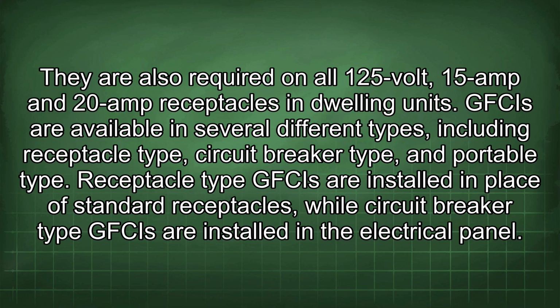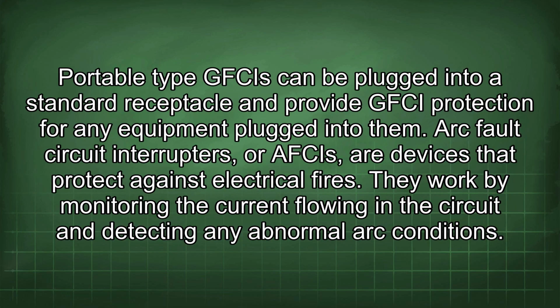Receptacle type GFCIs are installed in place of standard receptacles, while circuit breaker type GFCIs are installed in the electrical panel. Portable type GFCIs can be plugged into a standard receptacle and provide GFCI protection for any equipment plugged into them. Arc fault circuit interrupters, or AFCIs, are devices that protect against electrical fires.